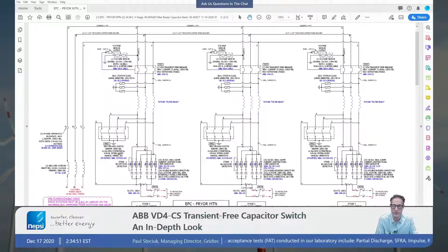So we're going to cross over and show a drawing of this VD4-CS incorporated in our design here at NEPSI. So I'm going to share my screen, and we'll come over to a quick PowerPoint, a quick PDF file. So this is a 3-stage capacitor bank consisting of 3 stages of 13.4 megavars. So it's quite a big bank, typical for renewable power plants. This is a 3-line diagram. Power cables come in through a set of roof bushings, and we got an overhead bus bar within our metal enclosed system. And we have 3 VD4-CSs here. And they feed the associated 13.4 megavar capacitor banks, 3 of them. So it's a relatively large bank.